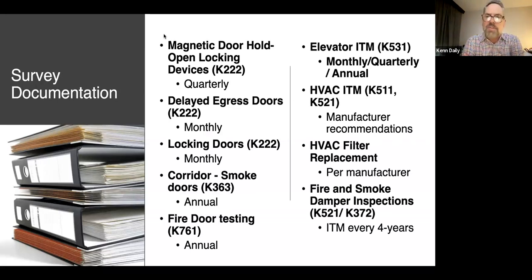And then you have delayed egress doors and locking doors. Again, during the fire alarm initiation, you make sure that these are all being unlocked so they completely stop functioning. But this is where the doors are permitted to slow someone down. Egress is, of course, the most basic fundamental of the code: to get out of a building, period. So this is permitting, because of psychiatric needs or the cognitive loss needs of your residents, that you are permitted to slow down the egress slightly based on a number of circumstances. But you got to make sure those doors function appropriately, and that's going to be under K tag 222.